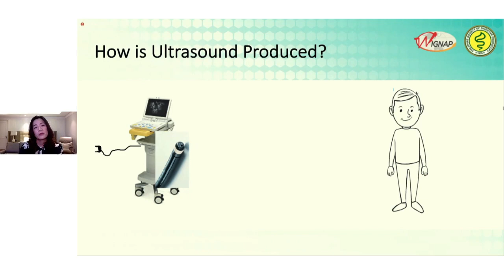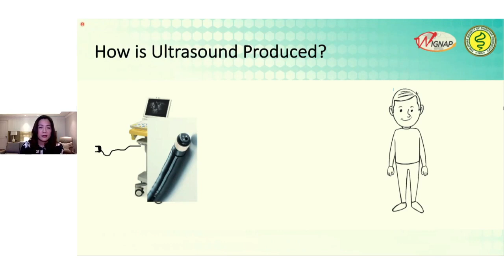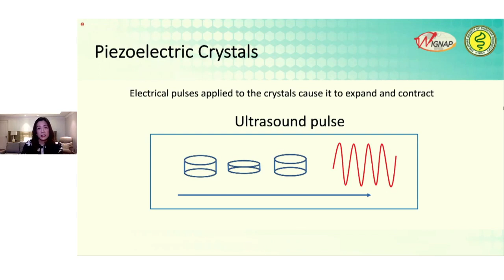Before we move forward, I want to talk briefly about the transducer at the tip of the endoscope. Located within the transducer are what we call piezoelectric crystals. These piezoelectric crystals receive electrical pulses, and when these electrical pulses are applied to them, the electrical pulses cause them to expand and contract. And this expanding and contracting of the crystal then results in transmission of ultrasound pulses.